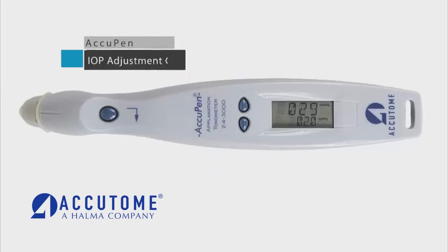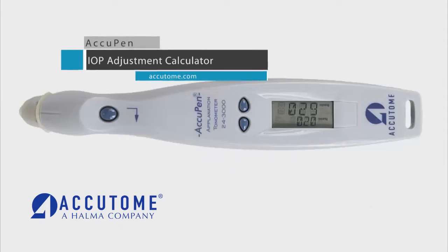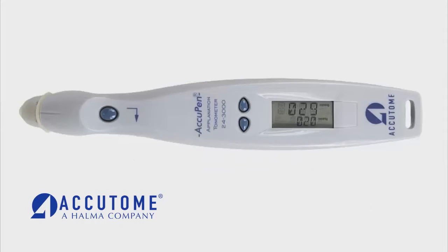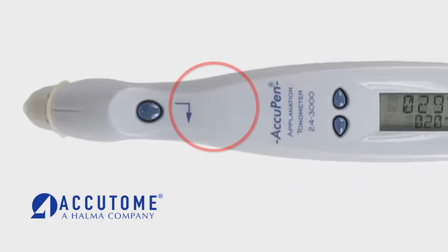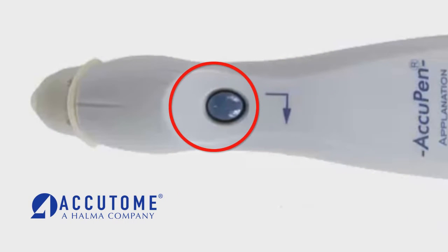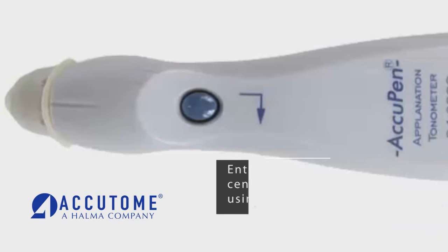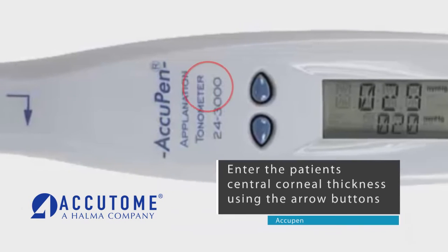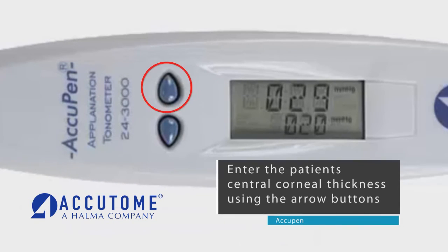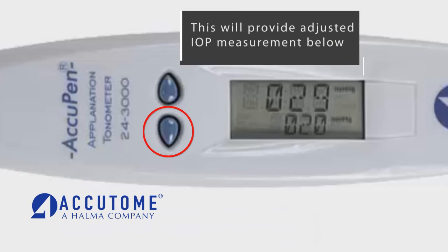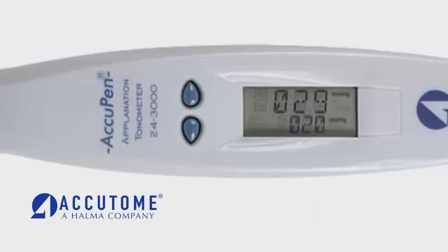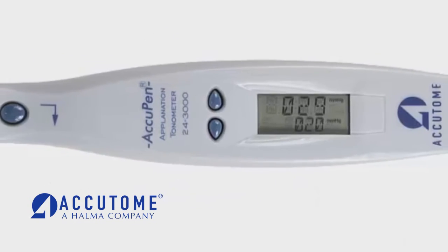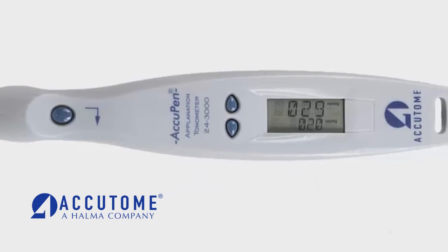The accupen also has an IOP adjustment calculator. Hold down the action button for 3 seconds to enter the IOP adjustment mode. Enter the patient's central corneal thickness by using the arrow buttons to scroll up or down. Press and hold to increase or decrease thickness by increments of 10. It is important to note the accupen does not take corneal thickness measurements.